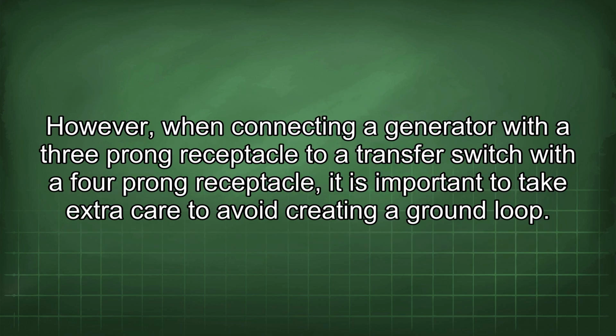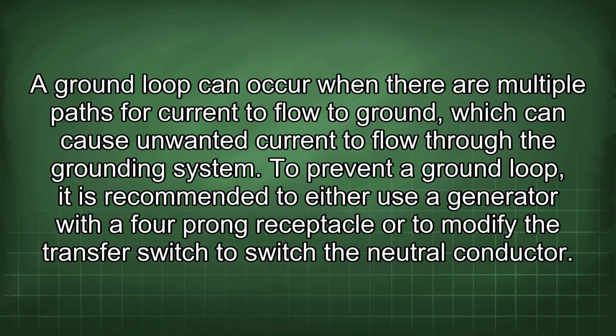However, when connecting a generator with a 3-prong receptacle to a transfer switch with a 4-prong receptacle, it is important to take extra care to avoid creating a ground loop. A ground loop can occur when there are multiple paths for current to flow to ground, which can cause unwanted current to flow through the grounding system.